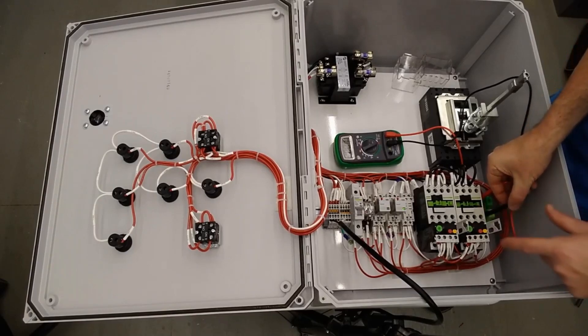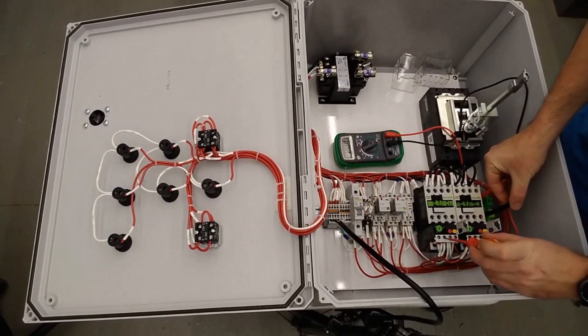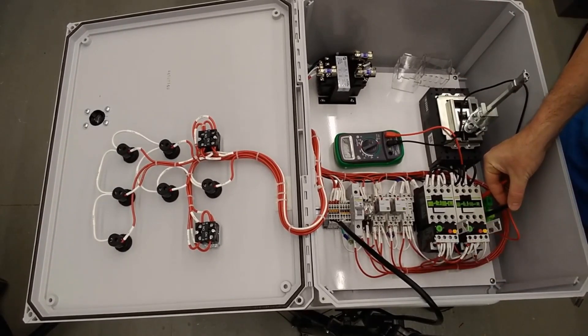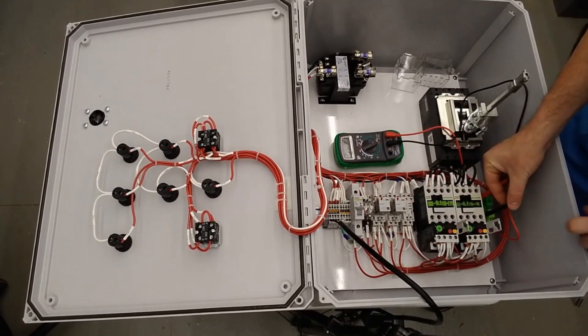You see we have continuity and I am just going to hit one of the tests on these motor starters and you can see that relay drops out and also our continuity drops out because now we have a fault.